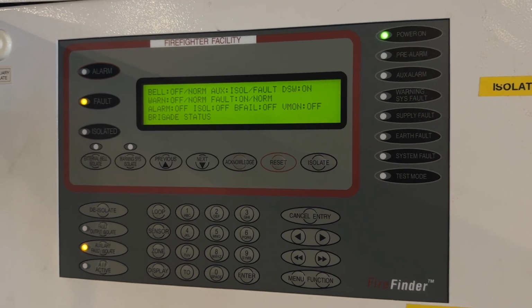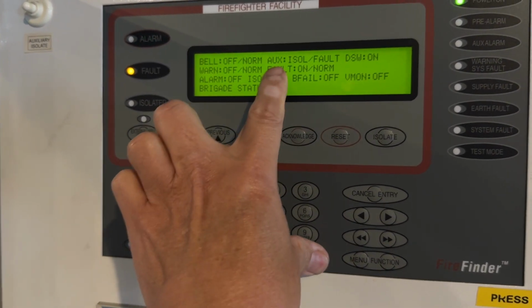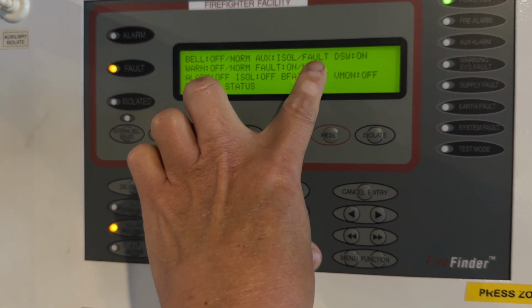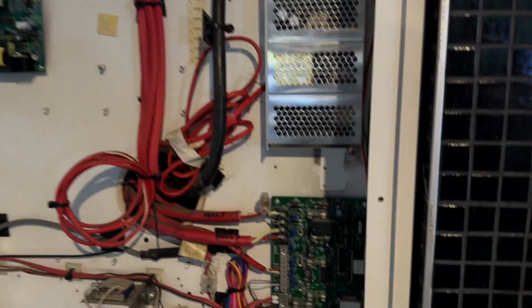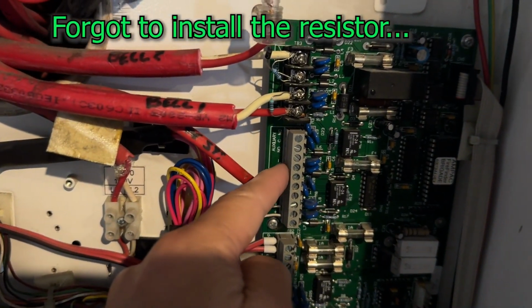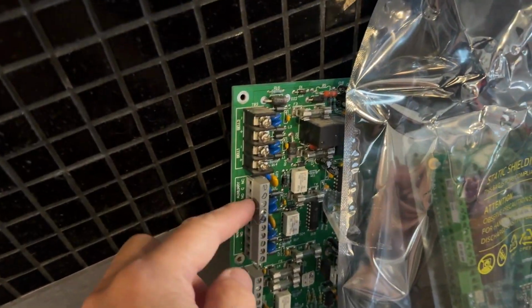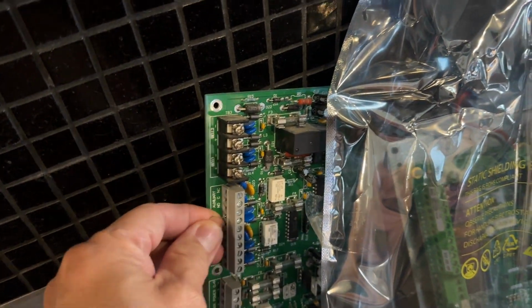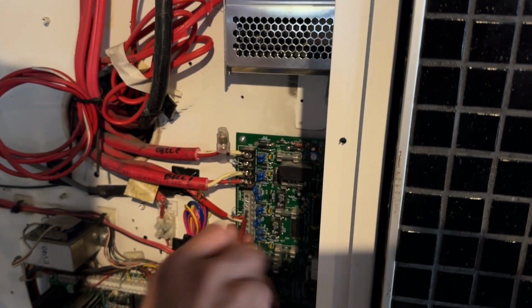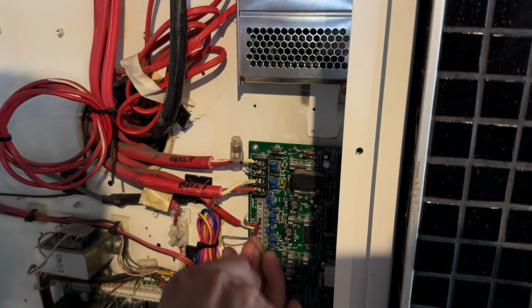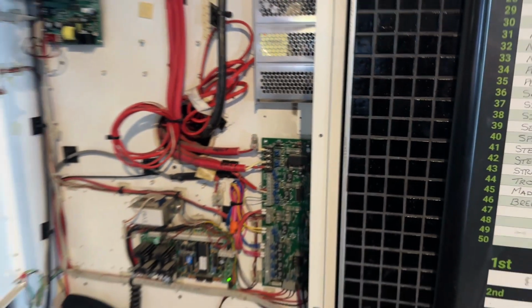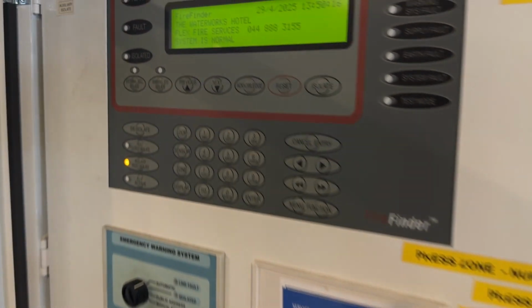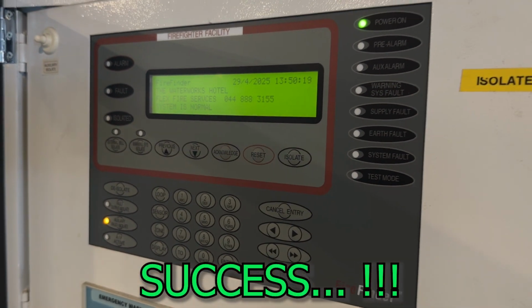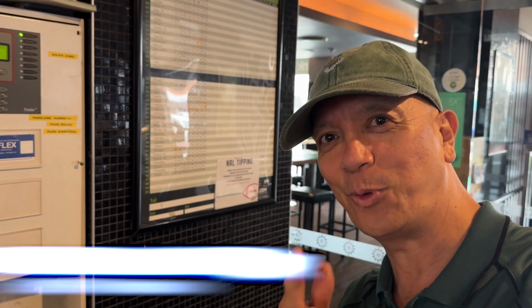Okay, we have a good result, except we have a fault, auxiliary isolation fault. So what's the problem? We have a missing resistor here. It's still in here. So we're going to put this there. Okay, installing the resistor. That should clear. Perfect.